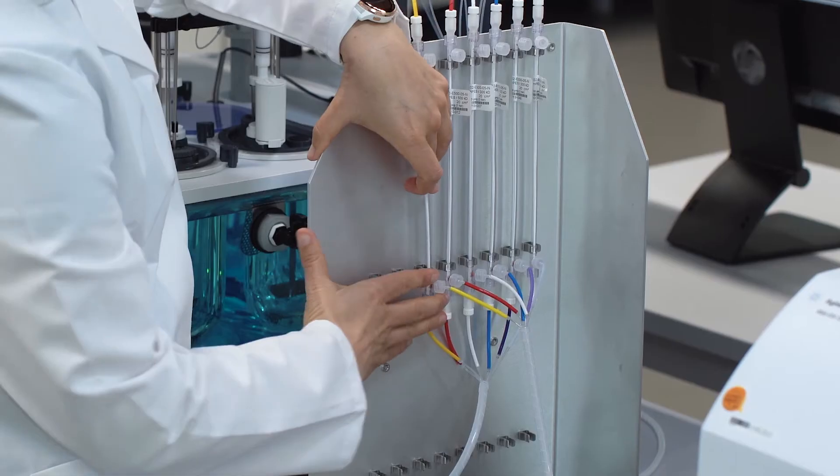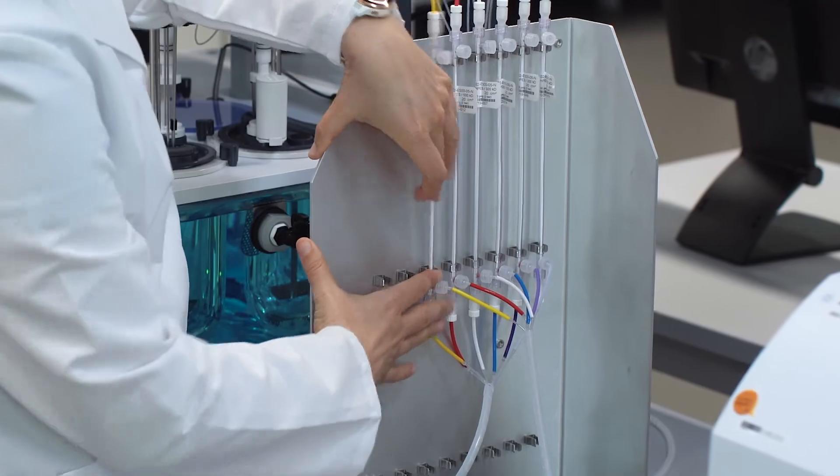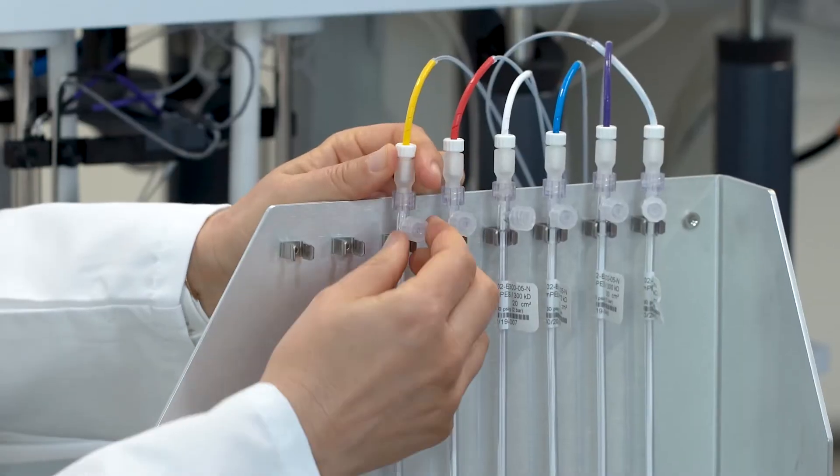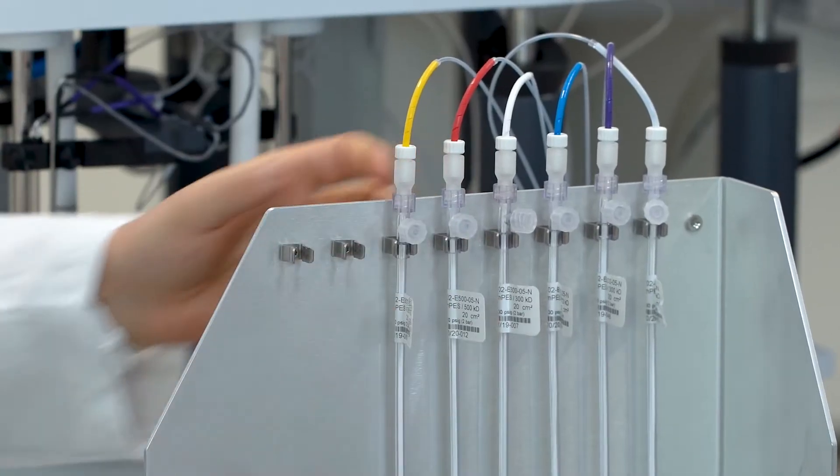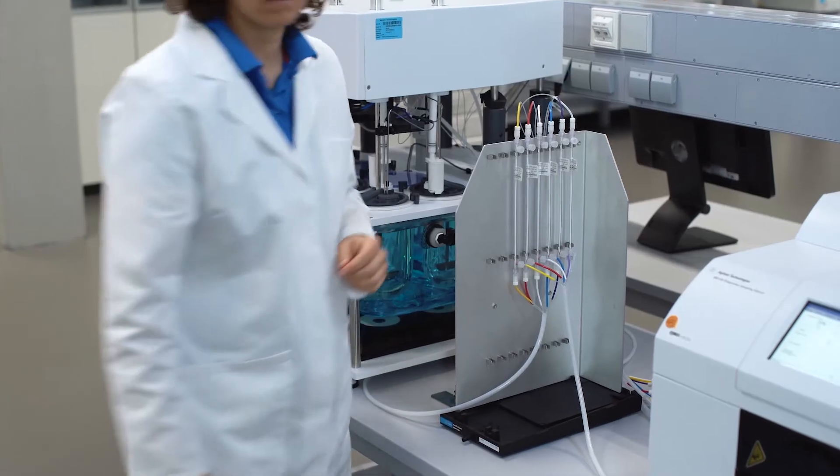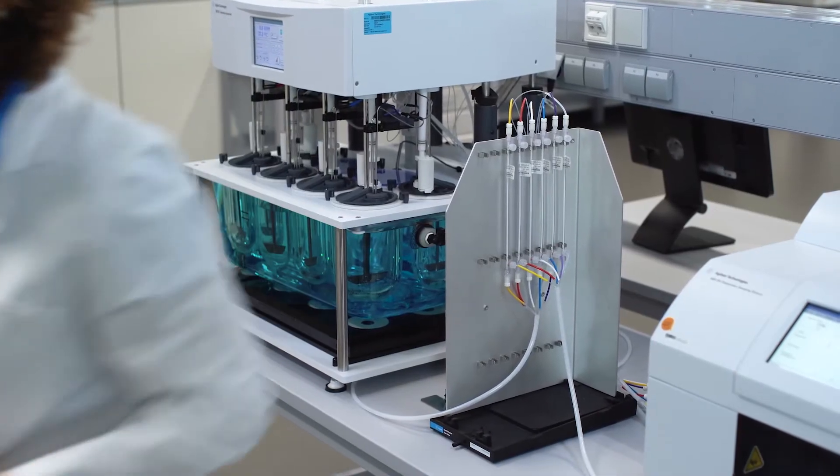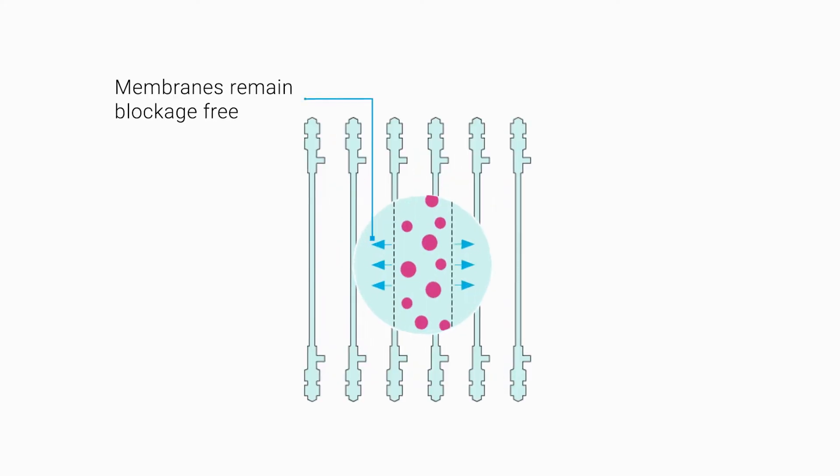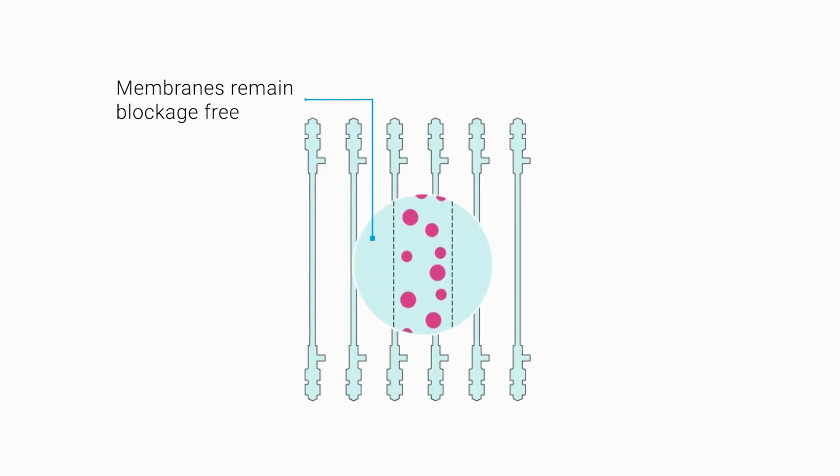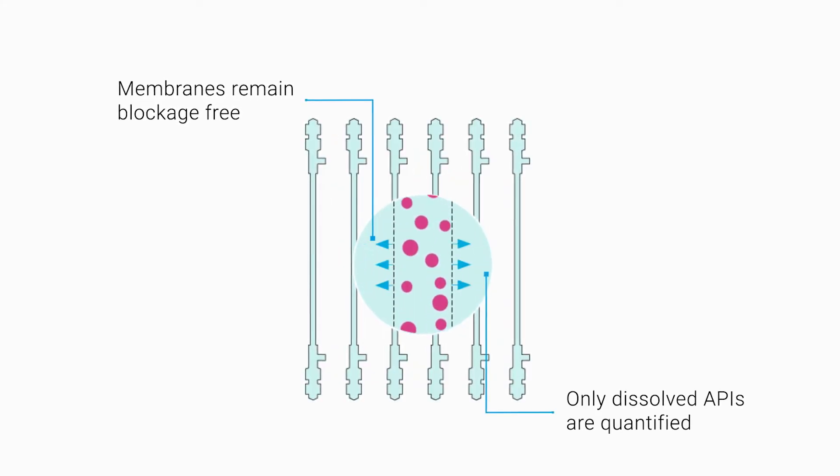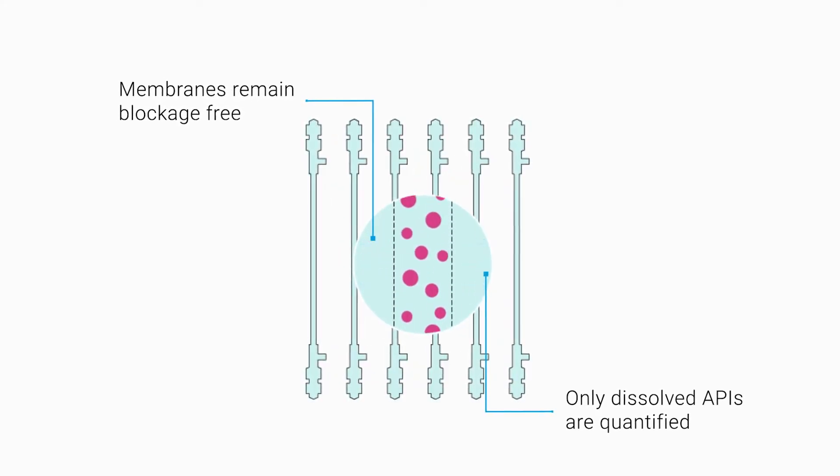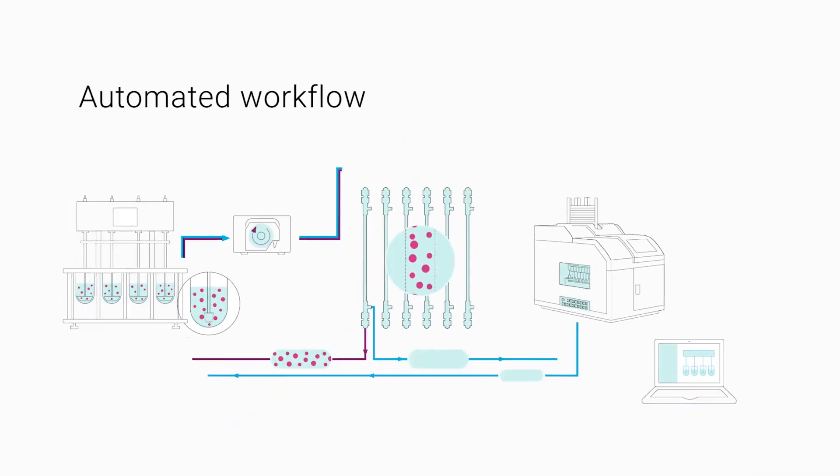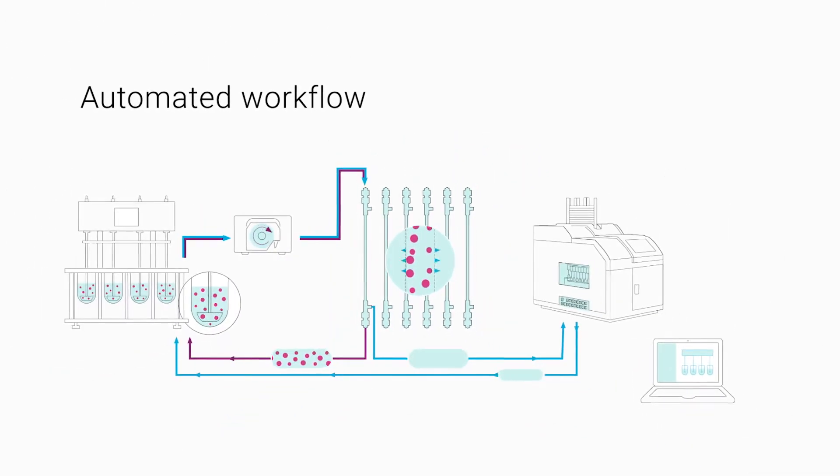Efficient cross-flow filters are used to speed up the filtration process and to increase test consistency. The filters provide blockage and rupture-free separation, ensuring that only dissolved APIs are quantified.